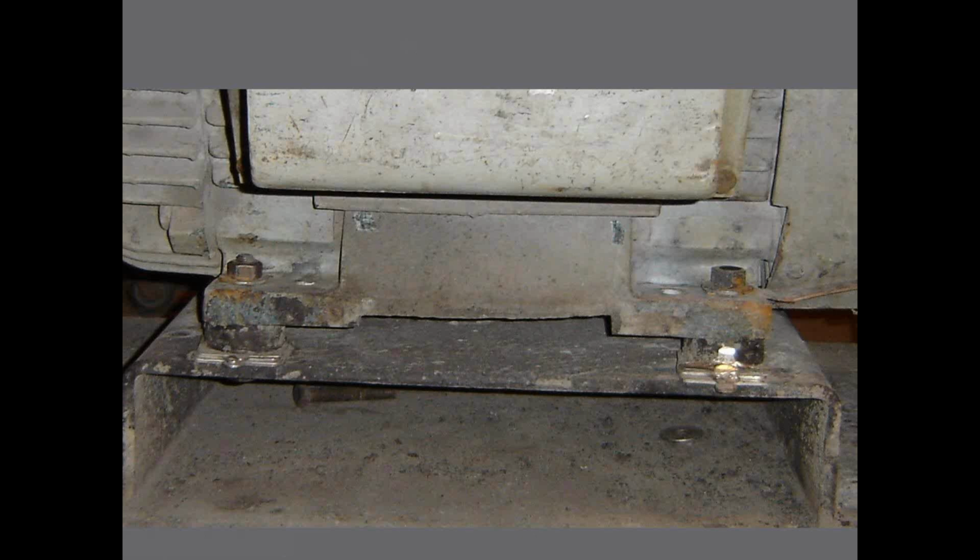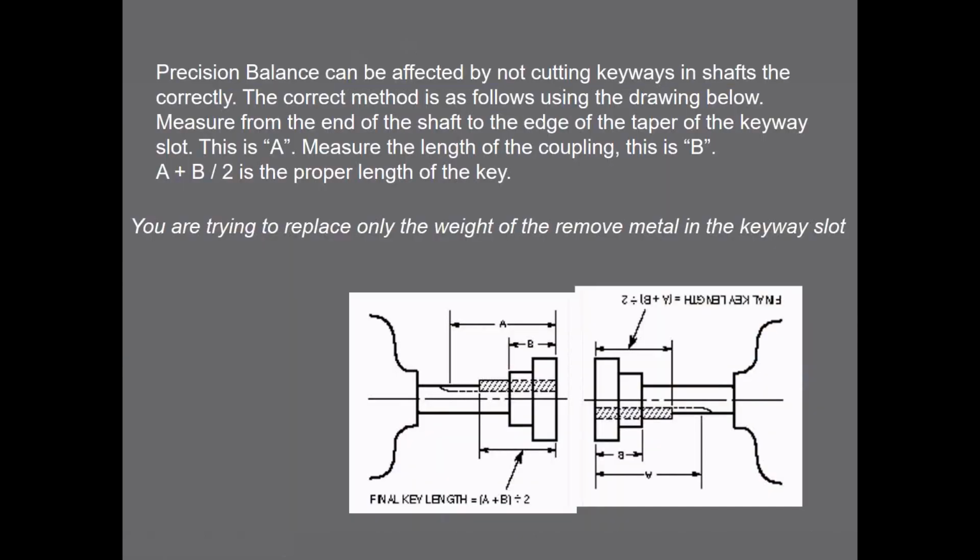But when I look at this picture, how long will this motor have stayed in alignment? Probably till they started it, because there's too many bad practices here that are not precise.